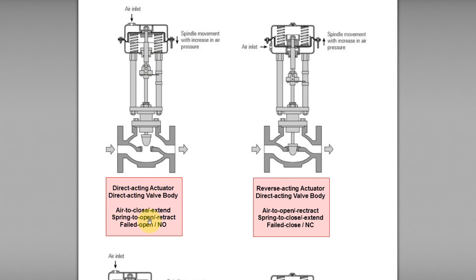Why is it also called spring to open, spring to retract, or fail-open? Because when the air is cut off, the compressed spring bounces upward. As a result, the stem or spindle moves upward or retracts outward. It is called fail-open because when you cut off the air, the plug moves outward and opens the valve body.